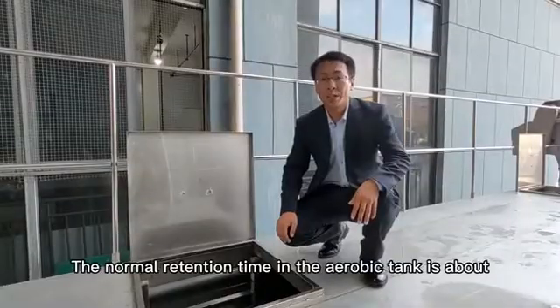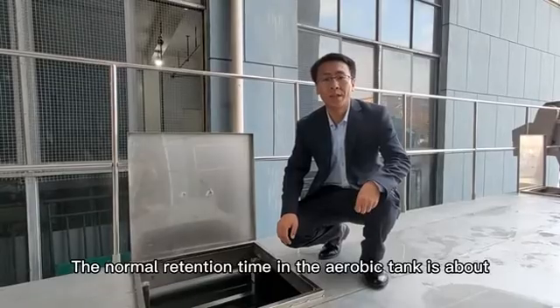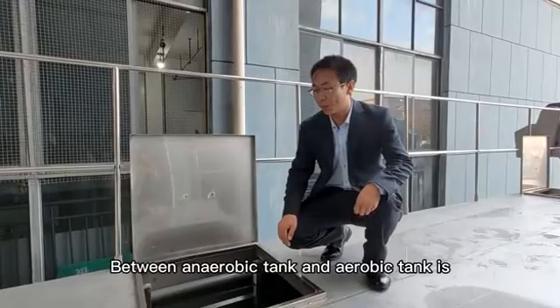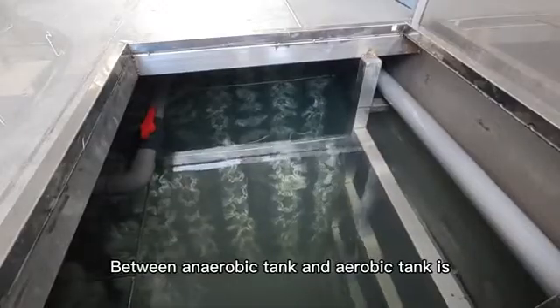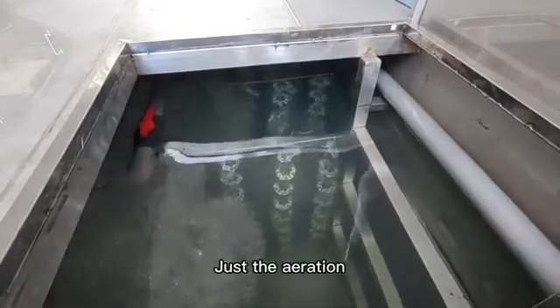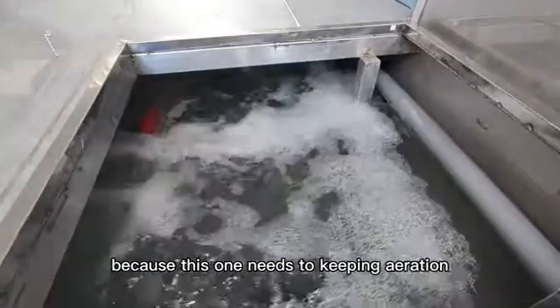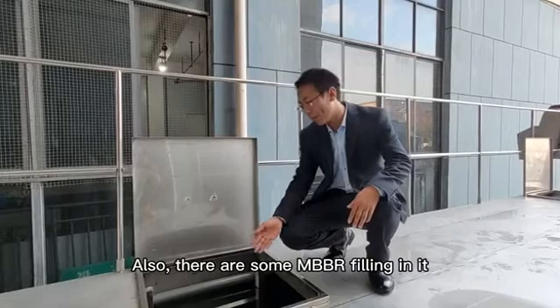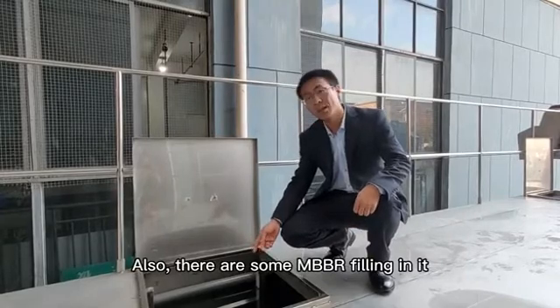The normal retention time in the aerobic tank is about four to six hours. You can see the difference between the anaerobic tank and the aerobic tank is just the aeration — this one needs to be kept aerated. There are also some MBBR filling in it.